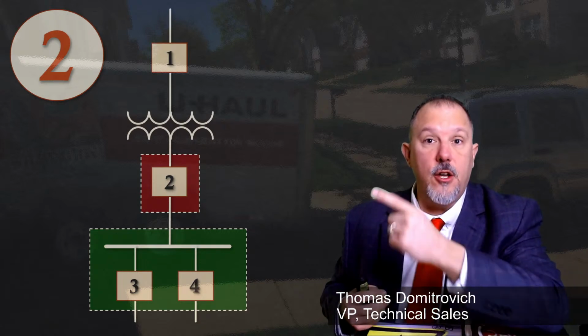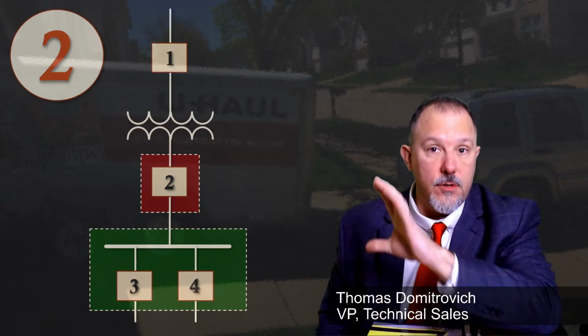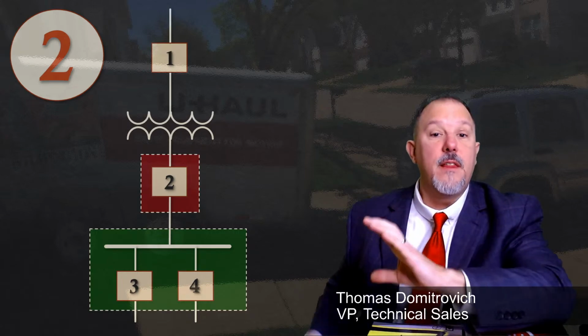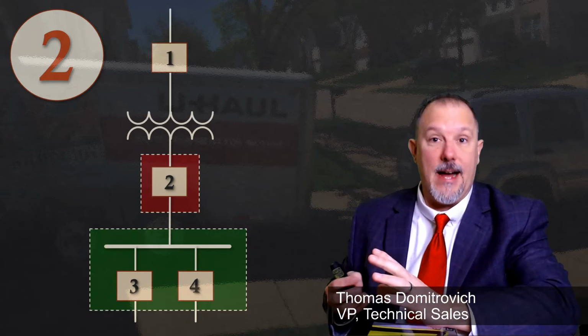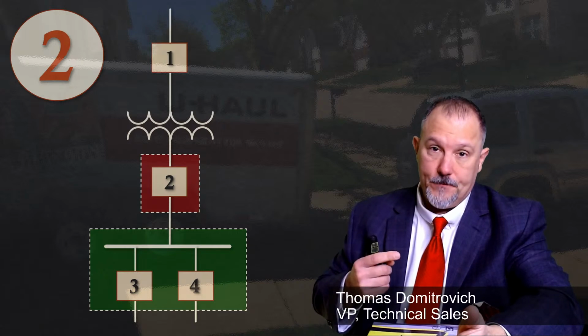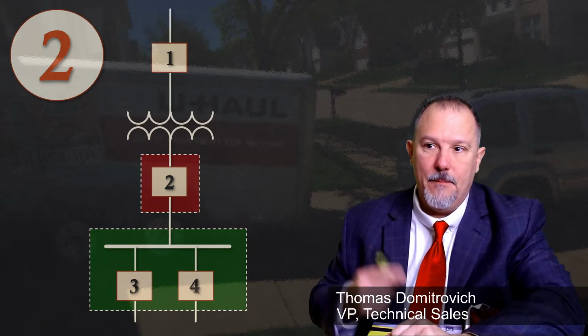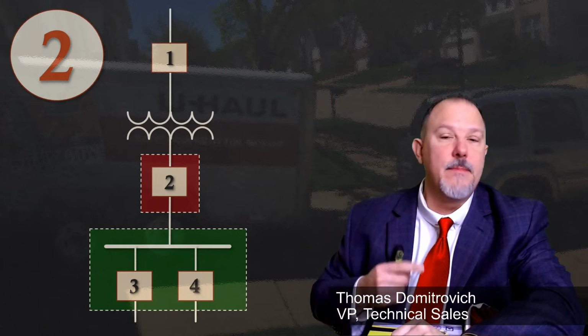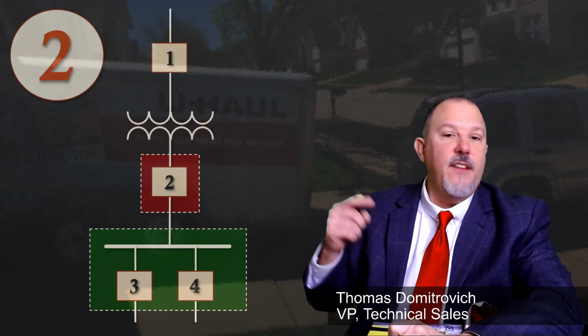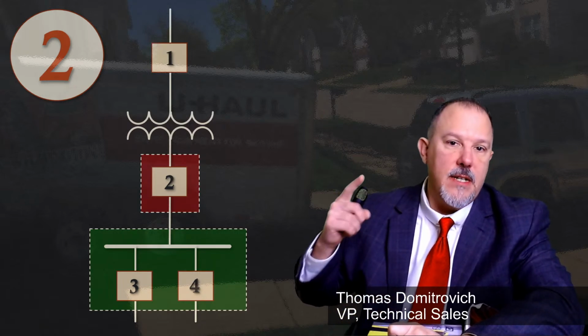One, you take advantage of the arc reduction technology, the overcurrent device that's in that little separate red box. The incident energy in that box is going to be high, but the likelihood of you having to get into that box is slim to none. And if you do, you know you've got the device. Now this could be your service entrance equipment as well.